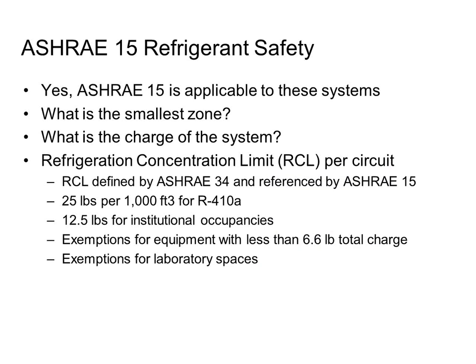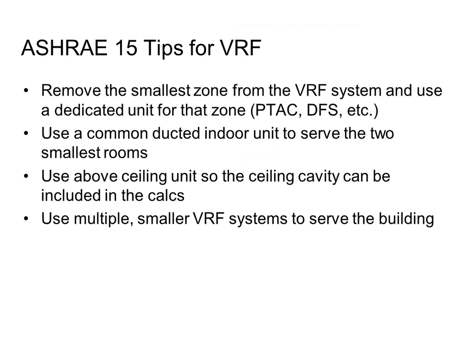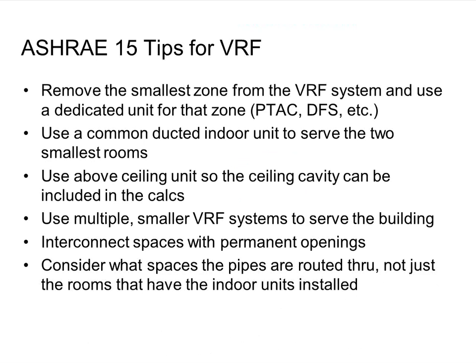And by the way, I should have mentioned that too, right? So when I have these tips on here of ways you can comply with ASHRAE 15, if you're above the limit, the other thing you could do is put refrigerant monitoring in, right? And then I can be as high as I want as long as I have refrigerant sensors that will alarm people and tell them to get the heck out of there.